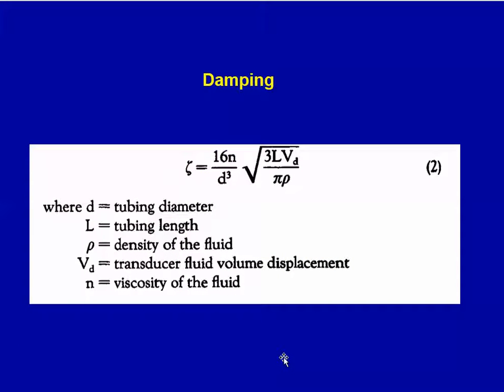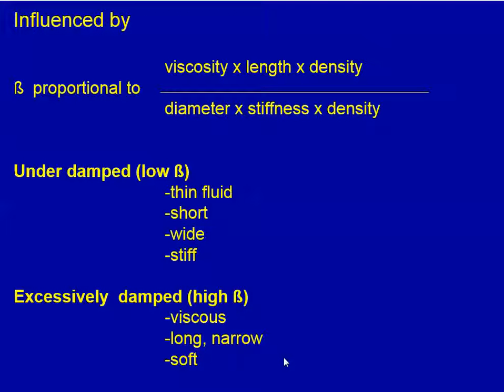These are the factors that influence damping. Basically, the damping coefficient is proportional to viscosity, length, and density over diameter, stiffness, and density. Things that cause the system to be under-damped include thin fluid, short tubing, wide tubing, and stiff tubing. Factors that cause excessive damping include viscous fluid, long narrow tubing, and soft tubing.